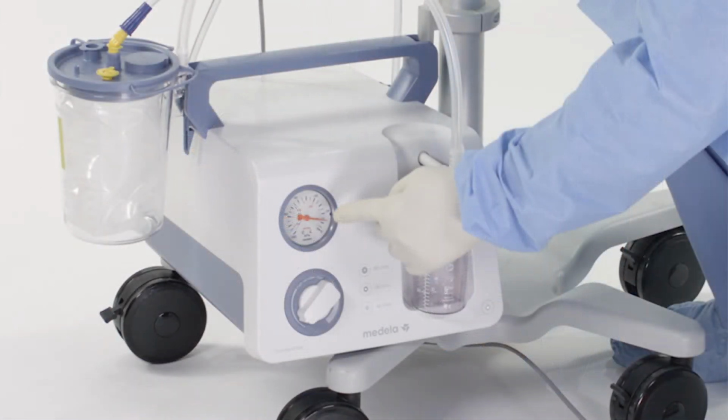It is important to confirm vacuum settings with physician. For a procedure in which tissue collection is desired, the vacuum should be 50 millimeters of mercury and can be increased as physician feels appropriate during the procedure. Do not exceed 250 millimeters of mercury.